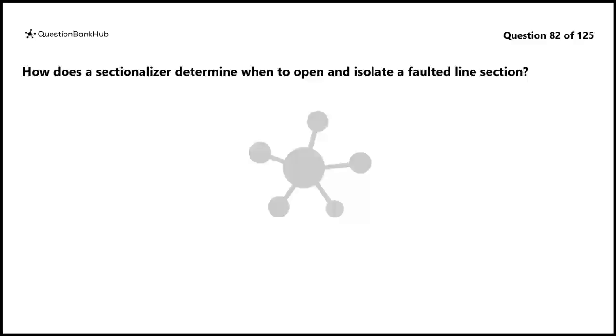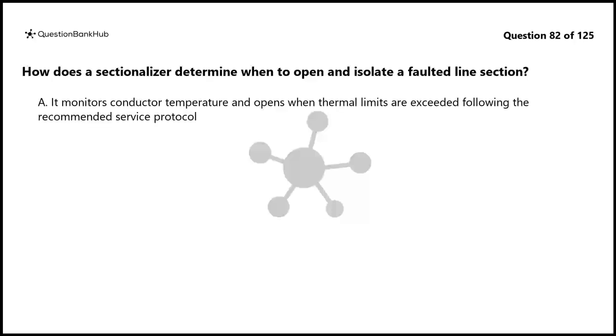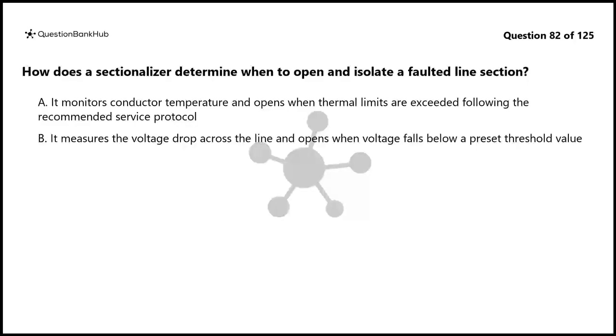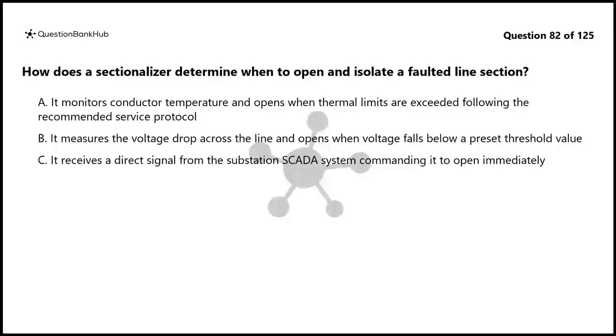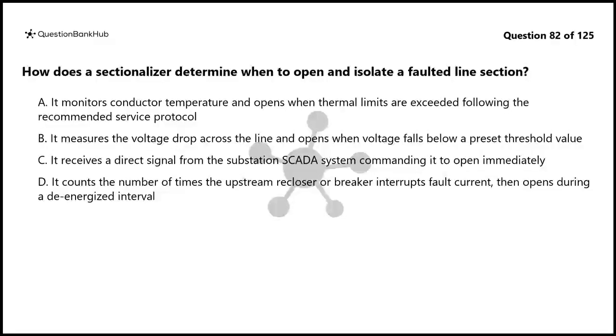Question 82. How does a sectionalizer determine when to open and isolate a faulted line section? A. It monitors conductor temperature and opens when thermal limits are exceeded following the recommended service protocol. B. It measures the voltage drop across the line and opens when voltage falls below a preset threshold value. C. It receives a direct signal from the substation SCADA system commanding it to open immediately. D. It counts the number of times the upstream recloser or breaker interrupts fault current, then opens during a de-energized interval.